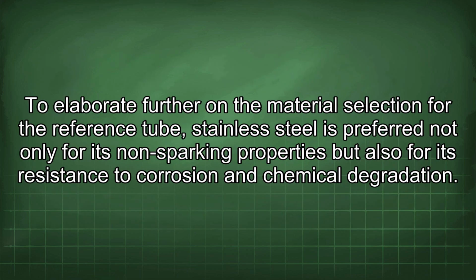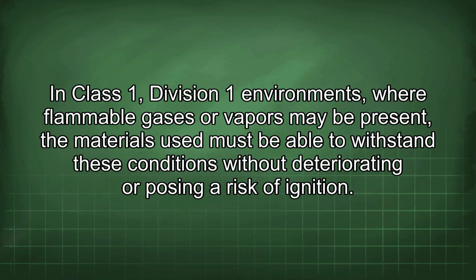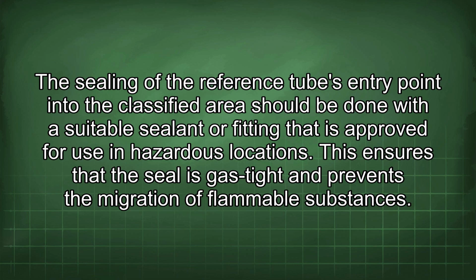To elaborate further on the material selection for the reference tube, stainless steel is preferred not only for its non-sparking properties but also for its resistance to corrosion and chemical degradation. In Class 1, Division 1 environments, where flammable gases or vapors may be present, the materials used must be able to withstand these conditions without deteriorating or posing a risk of ignition. The sealing of the reference tube's entry point into the classified area should be done with a suitable sealant or fitting that is approved for use in hazardous locations. This ensures that the seal is gas-tight and prevents the migration of flammable substances.